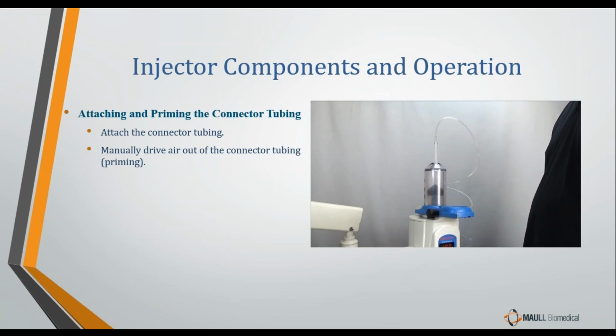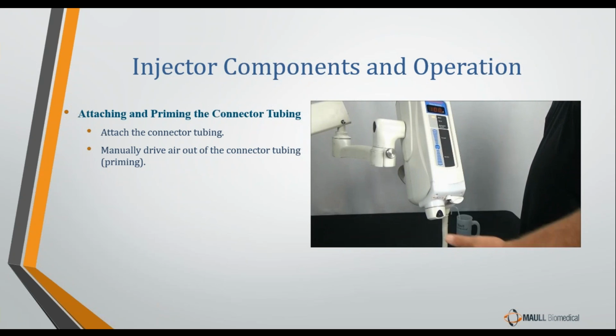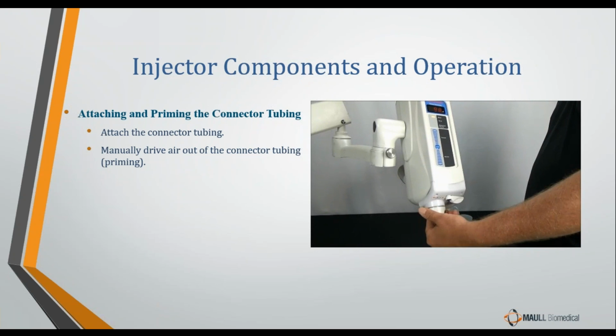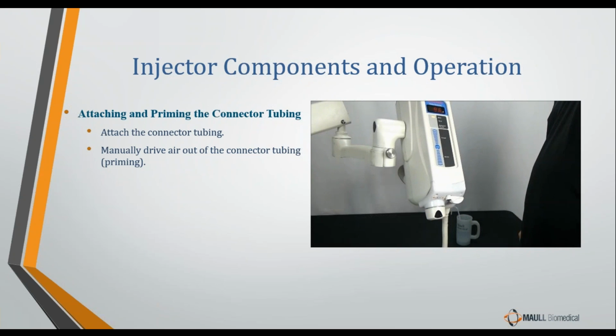Then using the manual knob, we will purge out any air that's in the connector tubing before we connect it to the patient, or for maintenance purposes, put it in our container to drain the fluid out. And we're all set. That is how you connect, fill, prime, and connect the syringe and connector tubing to the patient. When I teach all the time, I keep having the urge to ask if there's any questions. So if there's any pertinent questions popping up, let me know.